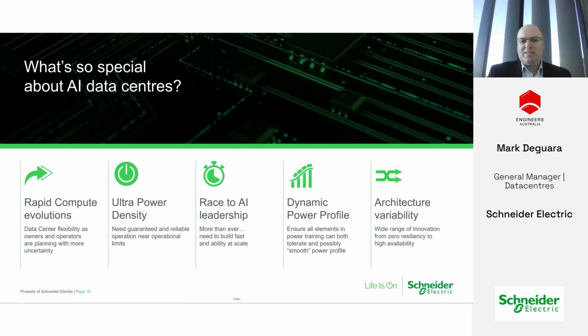Ultra power density - the density in a very small footprint. If we talk about a conventional rack, 600 or 800 wide by 1200 deep, and think we're going to fit a megawatt into that, or maybe two, that's 1200 amps a phase, 1500 amps a phase - that is considerable. And how do we reject that heat? How do we get that heat out?